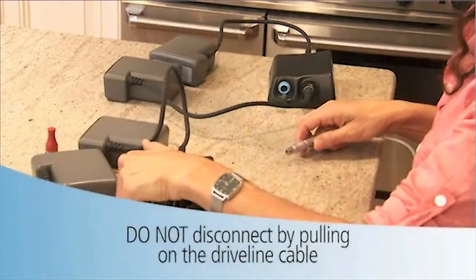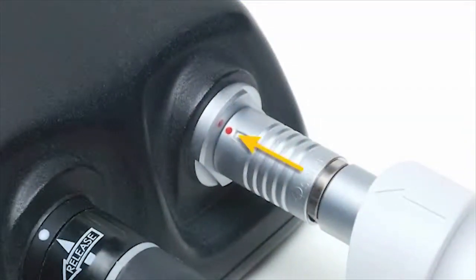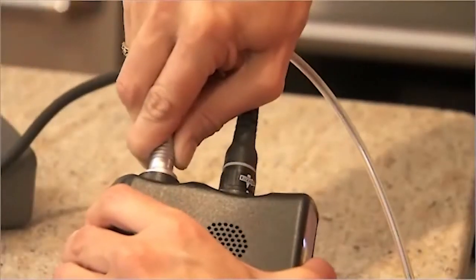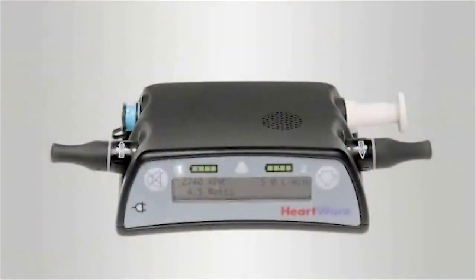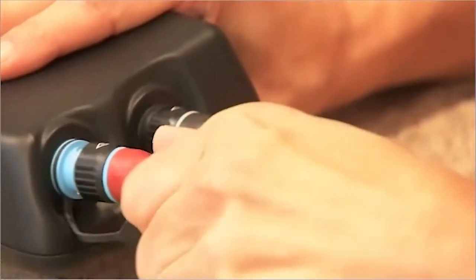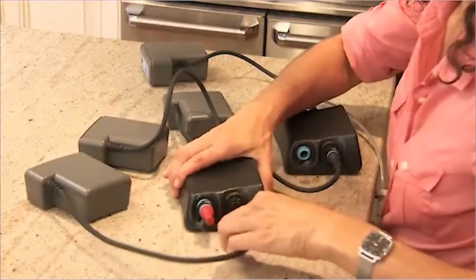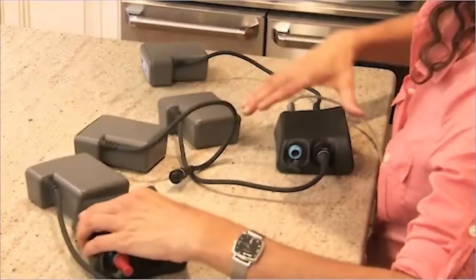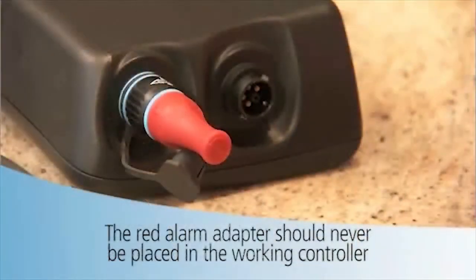Do not disconnect by pulling on the driveline cable. Connect the driveline to the new controller by aligning the two red marks and push together. The pump should restart. Verify the pump is working by checking the controller display for RPM, flow, and watts. Once you have verified that the pump is working, you can silence the VAD stopped alarm by inserting the red alarm adapter into the blue connector on the original controller. Then disconnect the power, silencing the old controller. The red alarm adapter should never be placed in the working controller.